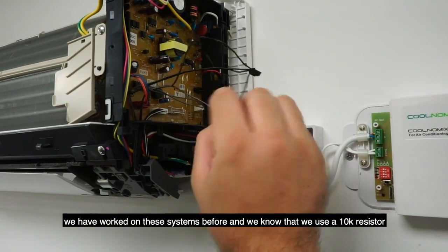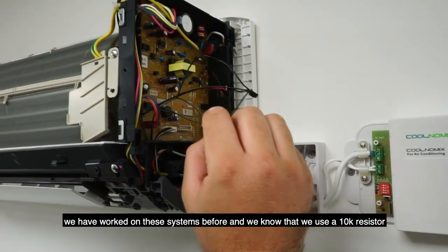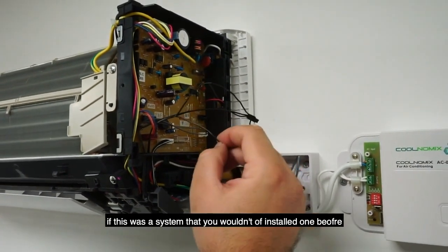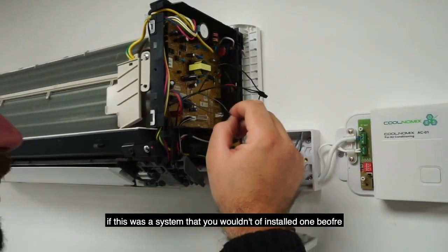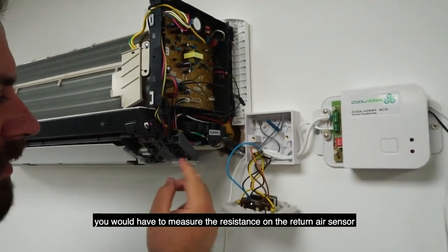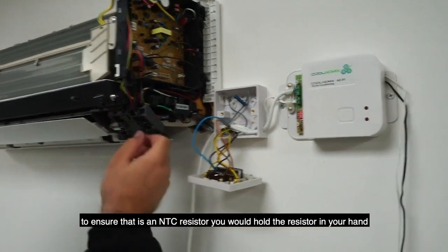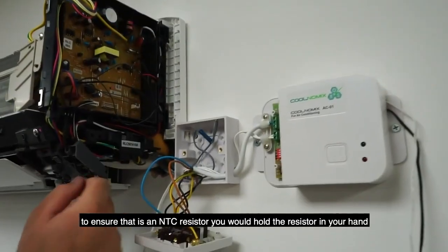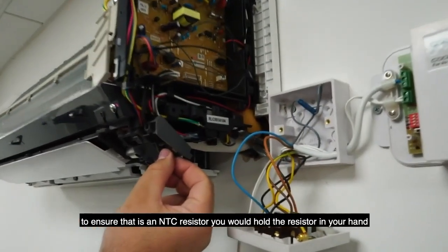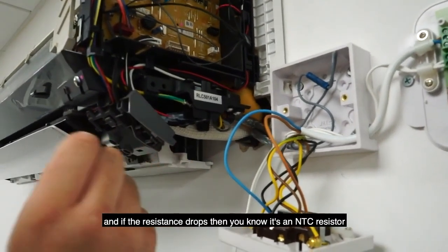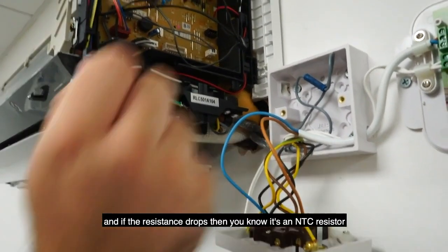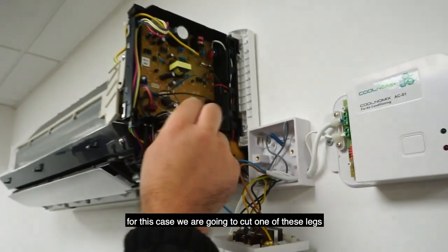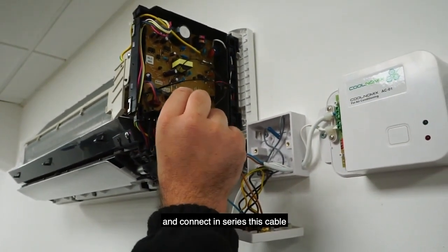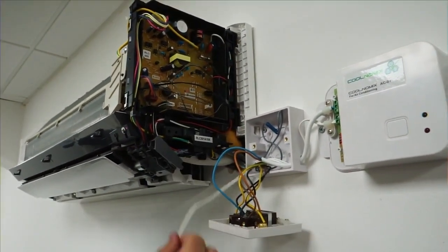We've worked in these systems before, and we know that we use a 10k resistor. If this was a system that you wouldn't have installed on before, you would have to measure the resistance on the return air sensor. To ensure that it's an NTC resistor, you would hold the resistor in your hand, and if the resistance drops, then you know it's an NTC resistor. For this case, we're going to cut one of these legs and connect in series this cable.